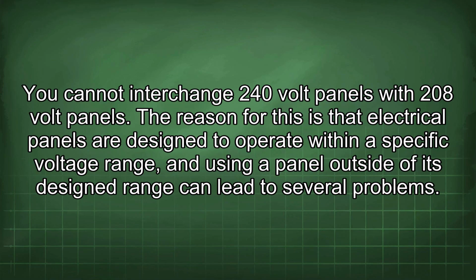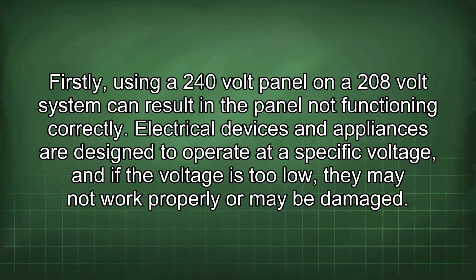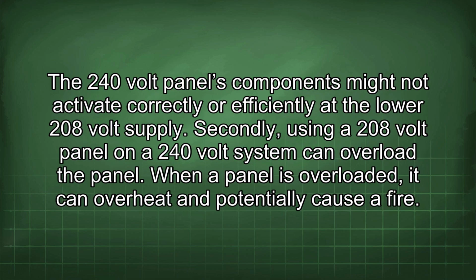You cannot interchange 240-volt panels with 208-volt panels. The reason for this is that electrical panels are designed to operate within a specific voltage range, and using a panel outside of its designed range can lead to several problems. Firstly, using a 240-volt panel on a 208-volt system can result in the panel not functioning correctly. Electrical devices and appliances are designed to operate at a specific voltage, and if the voltage is too low, they may not work properly or may be damaged. The 240-volt panel's components might not activate correctly or efficiently at the lower 208-volt supply.